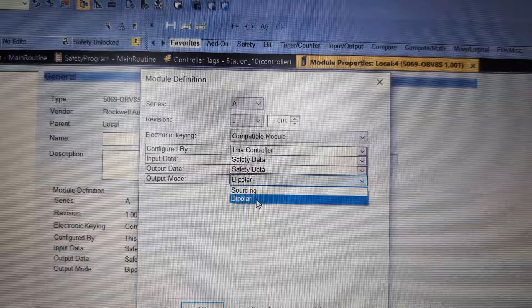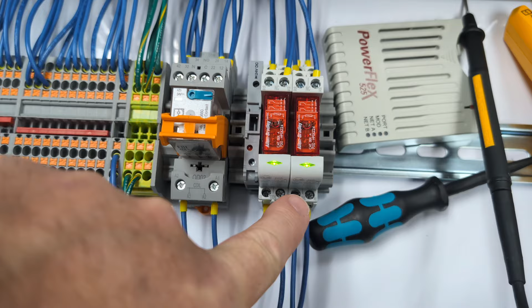So the only difference is now with this output, we have 2 flashing on it. But if I hit my safety reset, now all my channels light up, and both of my modules are lit up. This gives them a chance to see that on this one, the typical way is putting plus 24 volts from our output, and A2 going to the minus of our power supply. But this is a sinking output, so we're actually taking plus 24 volts to A1, and A2 is going up to our output module.